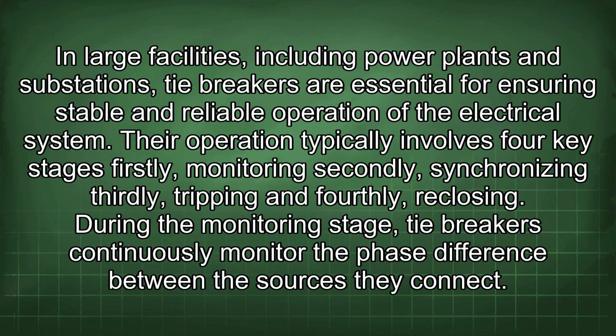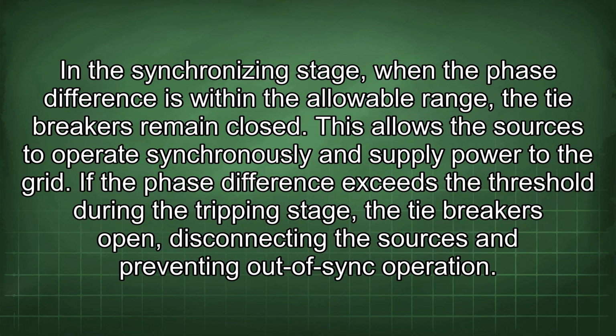In large facilities, including power plants and substations, tie breakers are essential for ensuring stable and reliable operation of the electrical system. Their operation typically involves 4 key stages: firstly, monitoring; secondly, synchronizing; thirdly, tripping; and fourthly, reclosing. During the monitoring stage, tie breakers continuously monitor the phase difference between the sources they connect. In the synchronizing stage, when the phase difference is within the allowable range, the tie breakers remain closed. This allows the sources to operate synchronously and supply power to the grid.